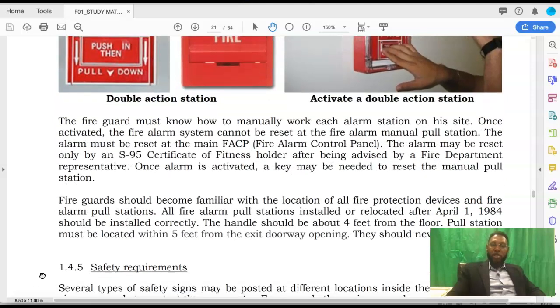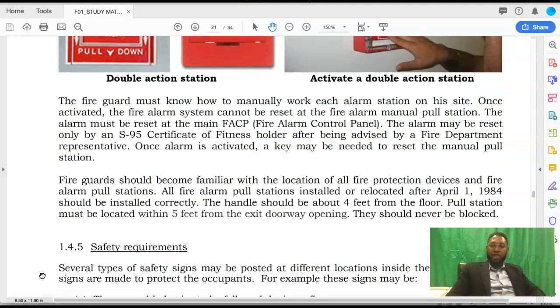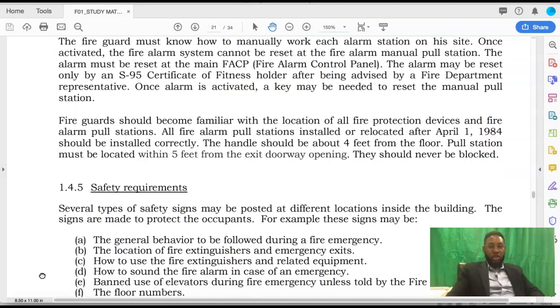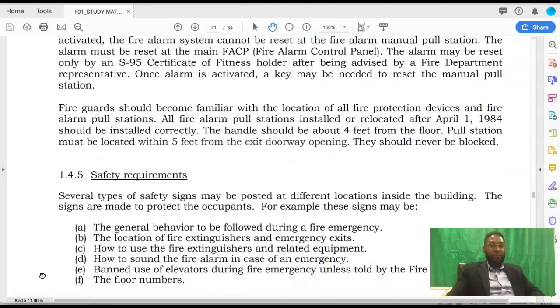So the fire guard must know how to manually work each alarm station. Once activated, the fire alarm station cannot reset itself. That's when the fire safety director becomes very important. The FSD. The FSDs are typically known as the S95 COF card holders. So once the alarm is activated, a key may be needed by the FSDs to reset the manual pull stations, with strict instructions from the brigaders in the fire department.